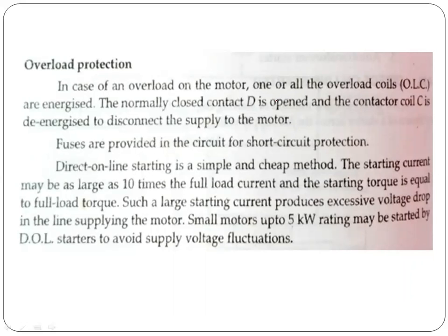Now direct online starting is a simple and cheap method. The starting current may be as large as 10 times the full load current and the starting torque is equal to full load torque. Such a large starting current produces excessive voltage drop in the line supplying the motor. Small motors up to 5 kilowatt rating may be started by a direct online starter to avoid supply voltage fluctuations. So, by a direct online starter, we can give under voltage protection, and we can give overload protection also.